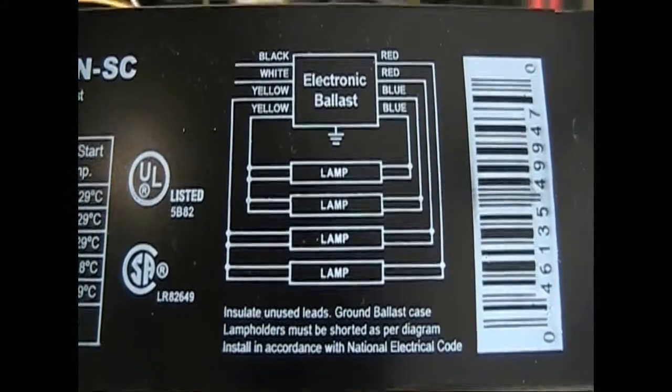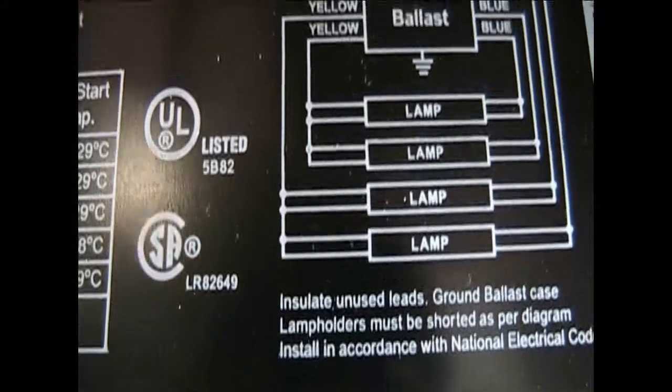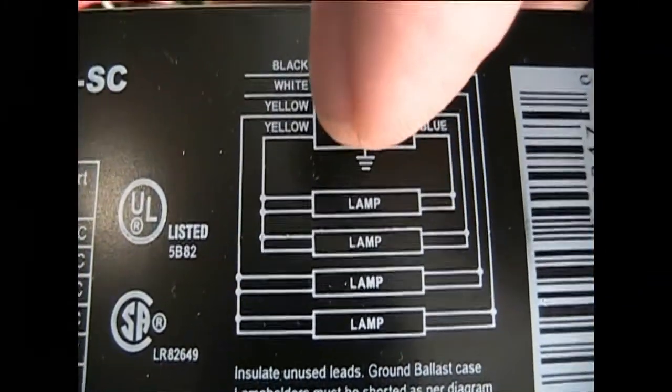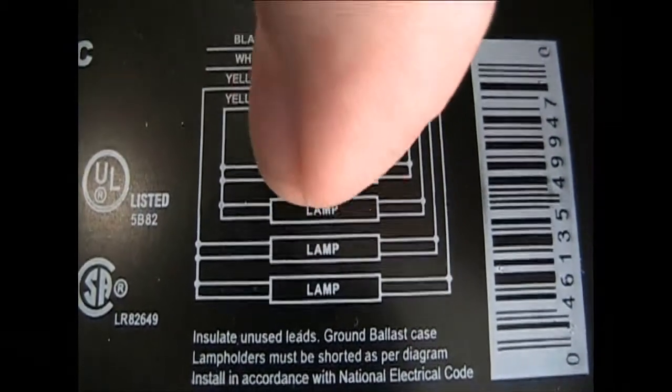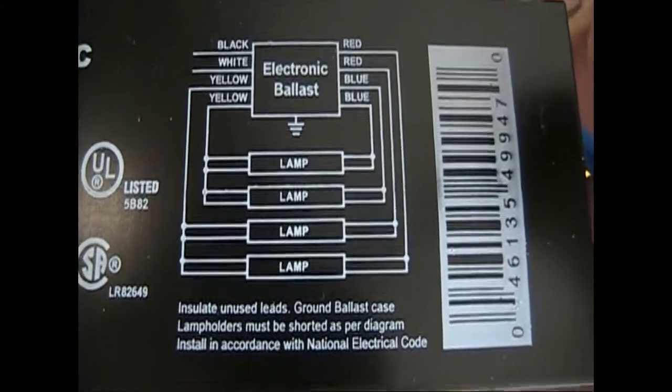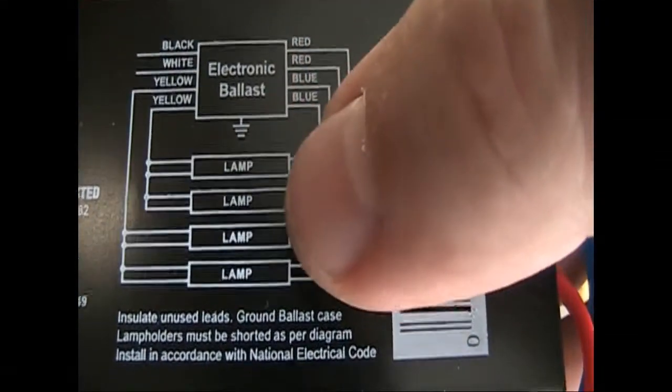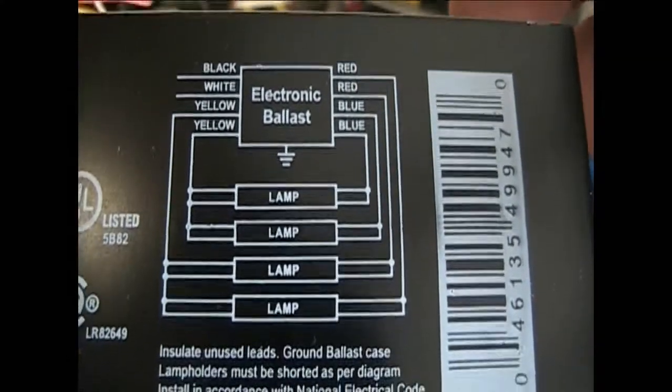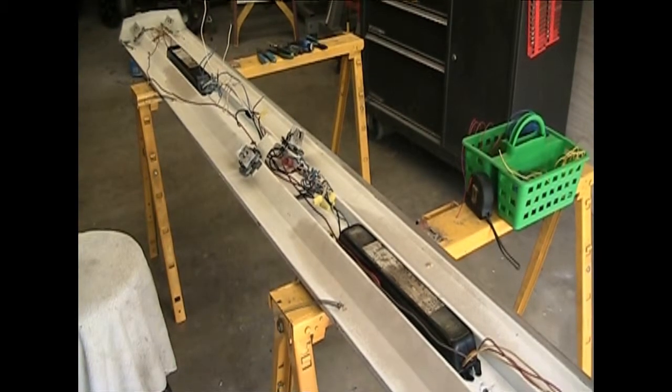First of all, on all ballasts there's a wiring diagram. As you can see, we have yellow that runs the bulbs that are jumped. One wire runs two bulbs. The other wire runs two bulbs. Then we have the red over here. That runs over and runs two bulbs. Then the blue runs two bulbs individually. So we're going to have to do a lot of jumping on the receptacles. I'll show you how that's done in a minute.